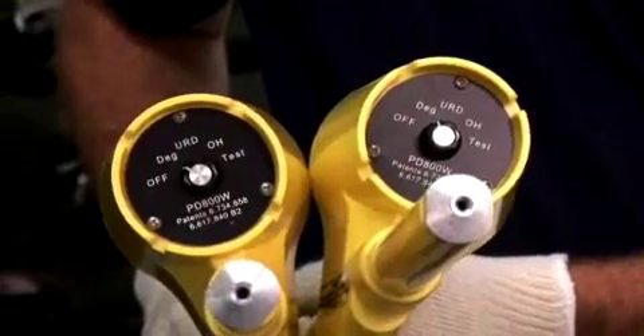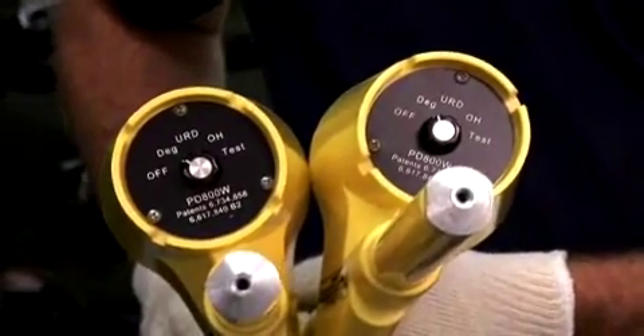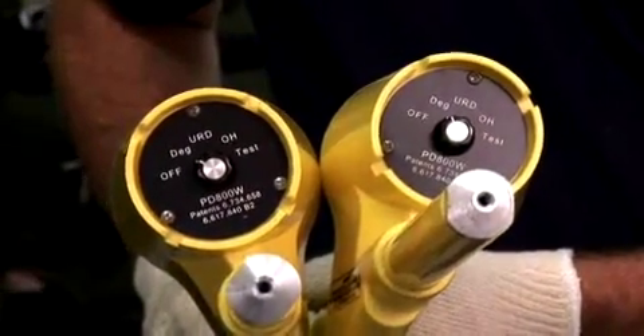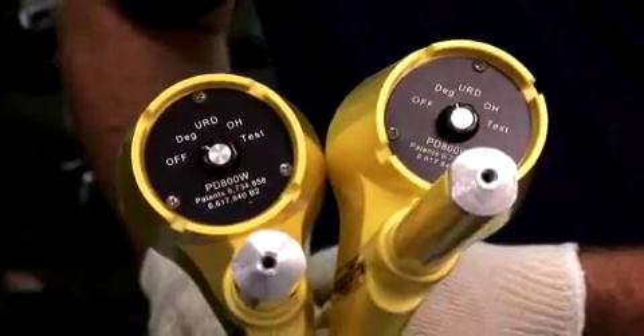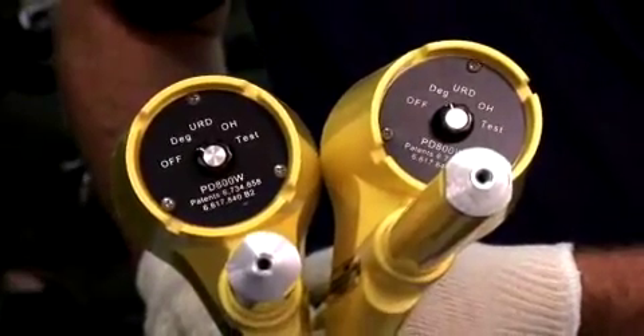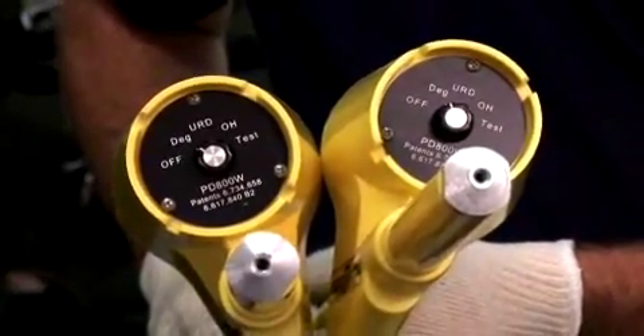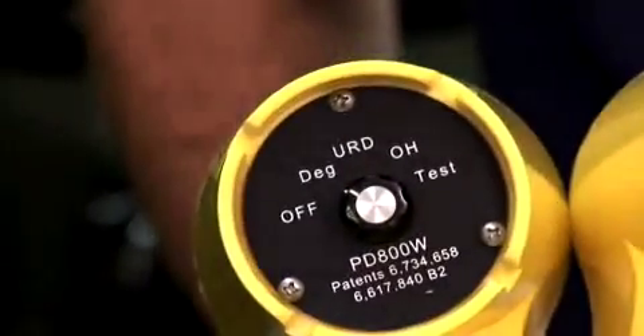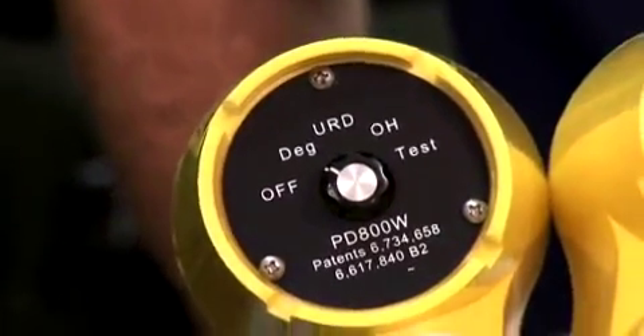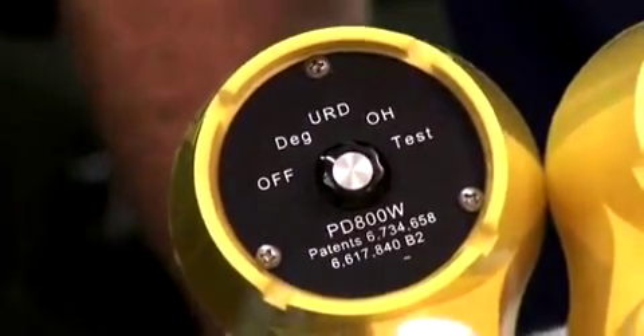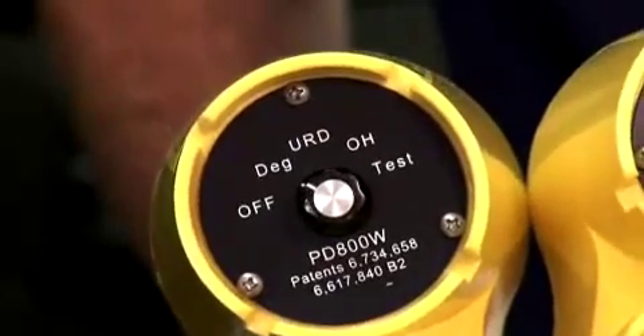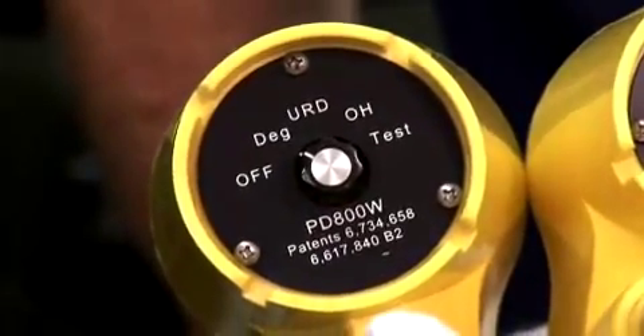5-position selector switch, off in the first position for storage and transit. Second position is DEG for angular degrees displacement between the phases. The third position is URD for underground voltage detection. Fourth position is overhead for overhead voltage detection. And the fifth position is to test the unit.